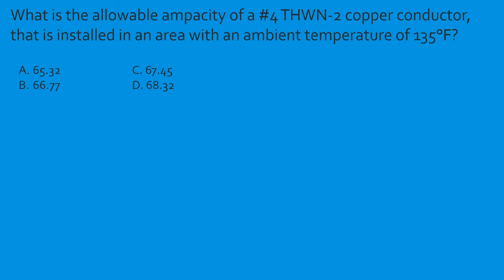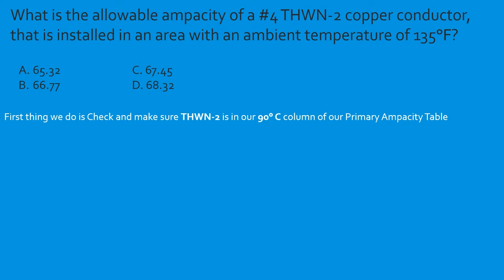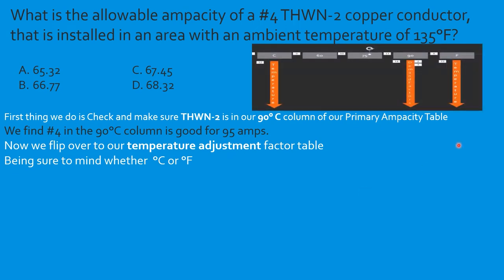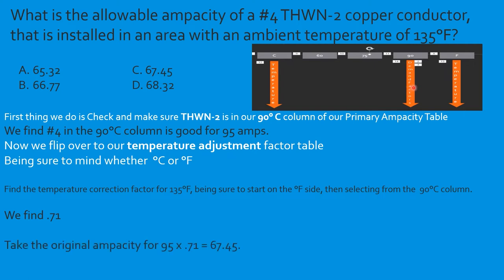Question: What is the allowable ampacity of a number 4 THWN-2 copper conductor installed in an area with an ambient temperature of 135°F? Confirm insulation is rated in the 90°C column. Number 4 in the 90°C column is good for 95 amps. Go to the temperature adjustment table, Fahrenheit side, find 135°F, tee off with 90°C — correction factor is 0.71. So: 95 × 0.71 = 67.45 amps. Select C.